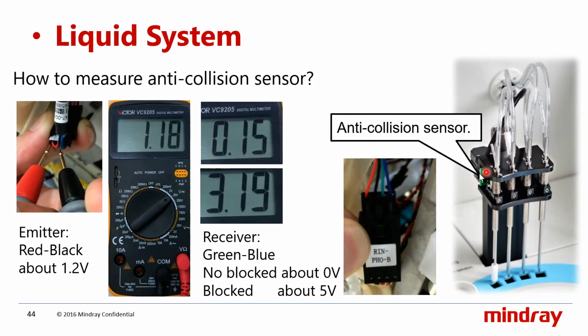So here there is a sensor, the wash station collision sensor. Most of you will face this issue. Suddenly the instrument will give an alarm, wash station collision error. Sometimes there won't be any vertical obstruction, but it will still trigger the alarm. So you need to check this sensor. There is a verification procedure.